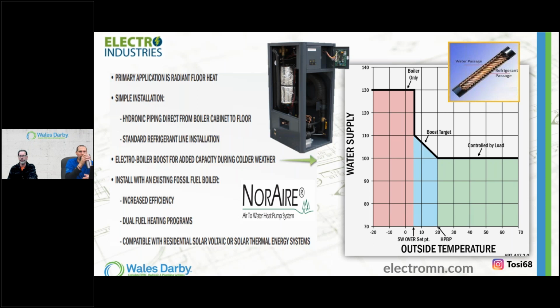Here's a chart again, showing you from right to left, with lowering outdoor temperature, what we can maintain with just refrigerant based, and then only then needed boost up, and then maybe full boiler only later. That's like 5 degrees outside. So for us around here, this is really starting to make sense for a lot of my already existing hydronic systems, especially with radiant.